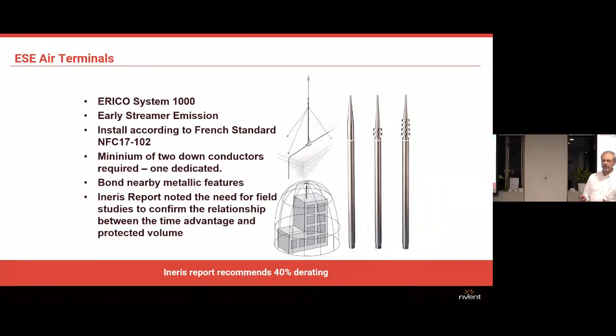So now we move away from the standard largely to active systems. An active system needs just one air terminal to cover a large area. Larger buildings will need more than one active system on them to be fully covered. We'll start off with the ESE air terminals. This is ERICO's System 1000, and ESE stands for Early Streamer Emission. This is designed according to the French standard NFC 17-102. And on the right there, you'll see that's the ERICO products, but this is made by a wide range of manufacturers around the world.